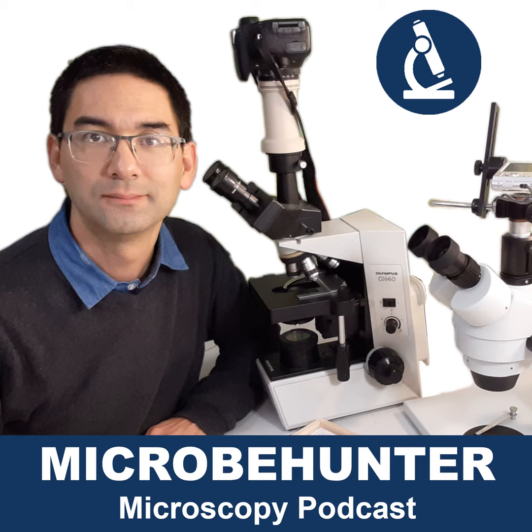The ergonomics refers to some health issues as well, because especially if you're using the microscope for a very long time, many hours a day, doctors do that, researchers do that, then you want to make sure that the microscope is designed using ergonomic considerations. So this can basically mean, for example, that the eye relief is large. So this means that the eye to eyepiece distance is larger. The size of the microscope might play a role here. So if the microscope is too small, for example, then you have to sit stooped over the microscope, and your back might start to hurt. The eye distance between the two eyepieces should be adjustable. Most microscopes actually have that. And some microscopes even allow you to adjust the tilt of the eyepieces, so that basically taller people can look into the microscope more from the top, and shorter people from more horizontally.